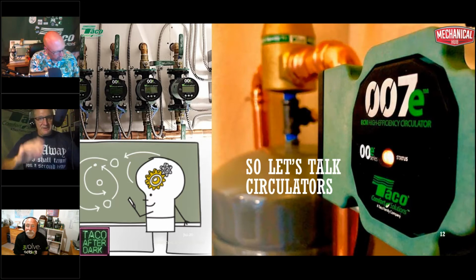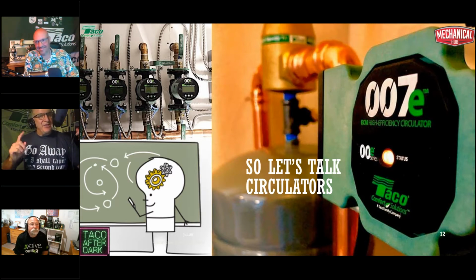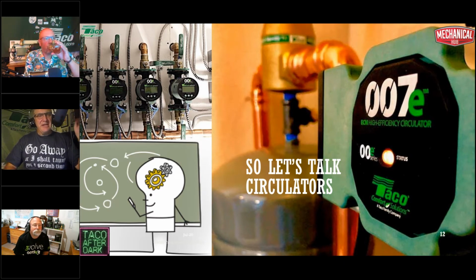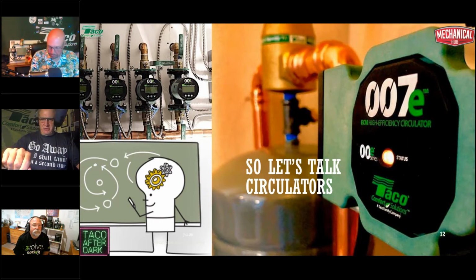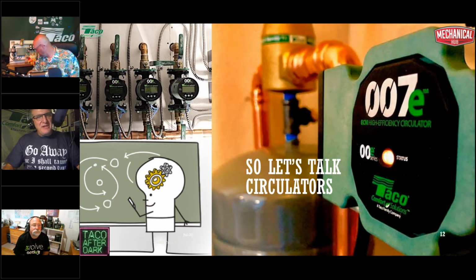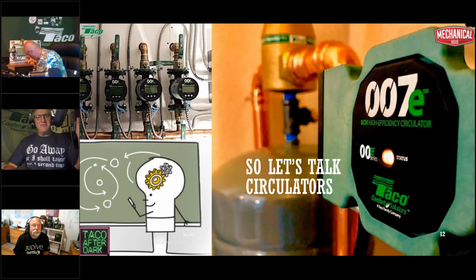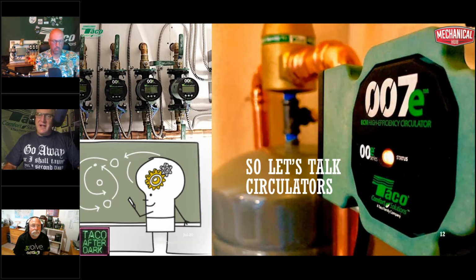I'm gonna go out on a limb here, and I know my two compatriots are gonna start rolling their eyes. But I think the days of the 3-speed pump are numbered. I think they're numbered because there's the convenience that we bought into of having a little switch that goes low, medium, high. Ooh, how about that? The convenience we bought into isn't worth it. All right, it's not worth it. The convenience is not worth the price that we're paying, not just to buy the pump, not just to run the pump, but the damage it does to the system. So I firmly believe 3-speed circulators are dead pumps walking. It's not going to be long.